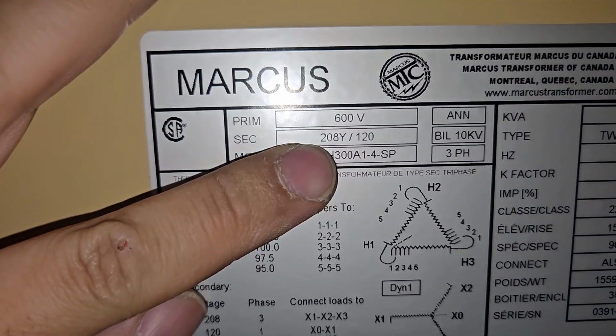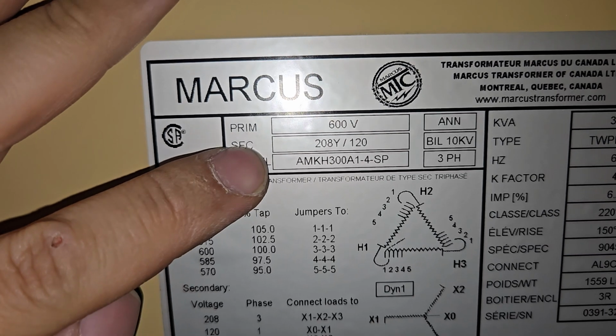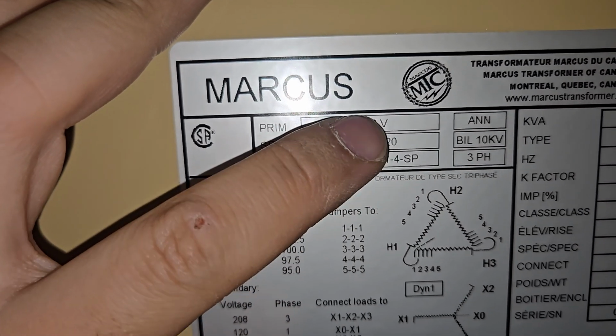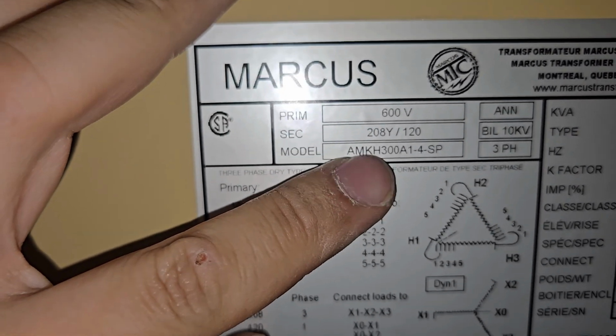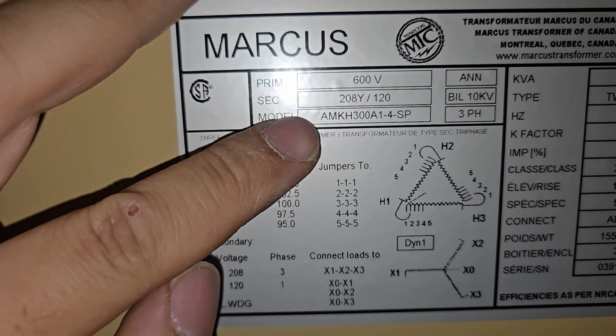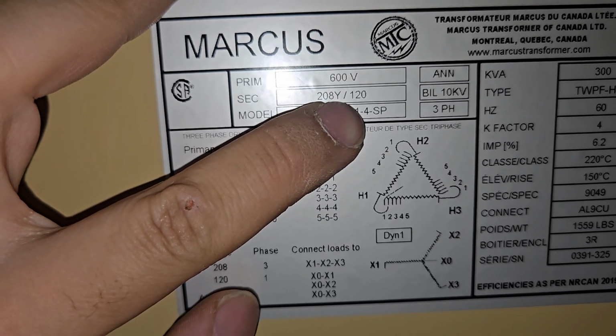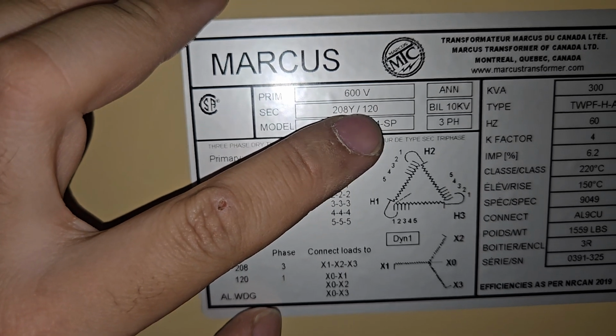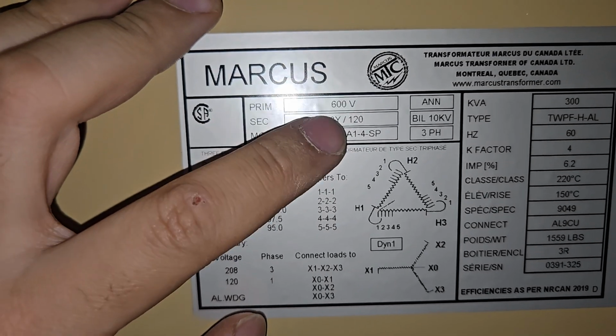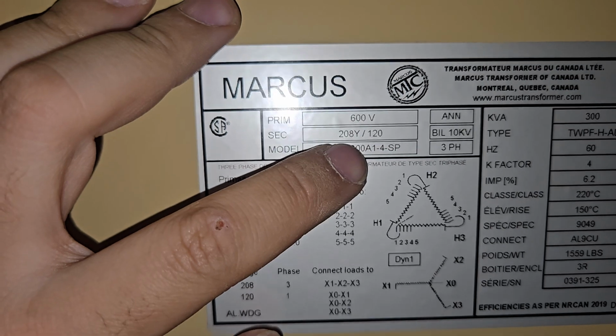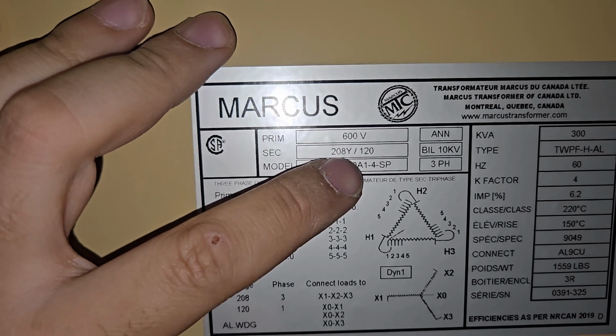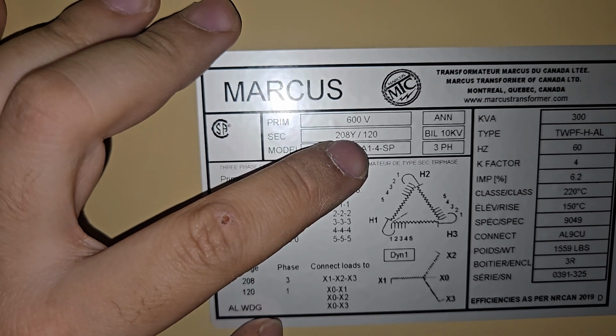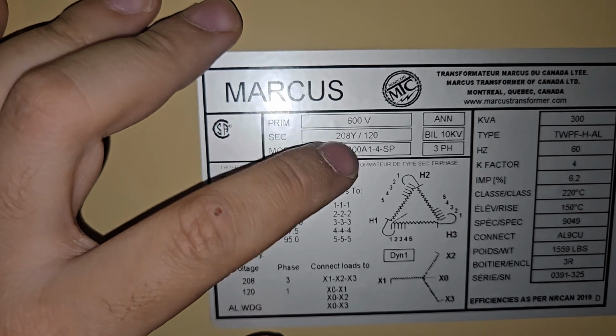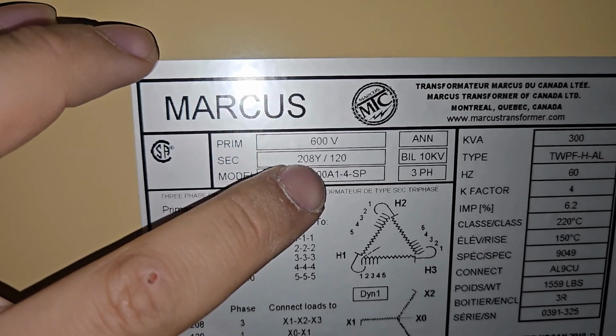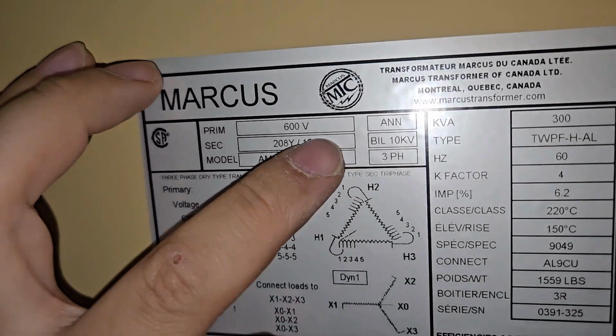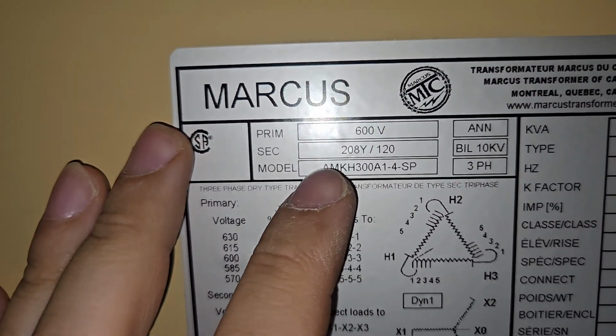You'll see primary voltage. So your primary voltage is 600 volts coming in, and then your secondary voltage is 208Y/120. So this tells you how the transformer was wired, and there's two ways to wire one. You can do Y or you can do delta, and that gives you a different voltage output when you have two wires, so a 2-pole breaker later on down the line. So you'll be careful of that.